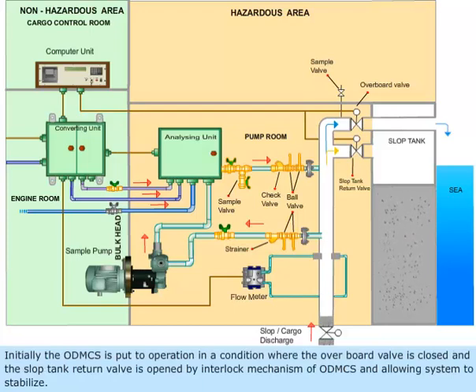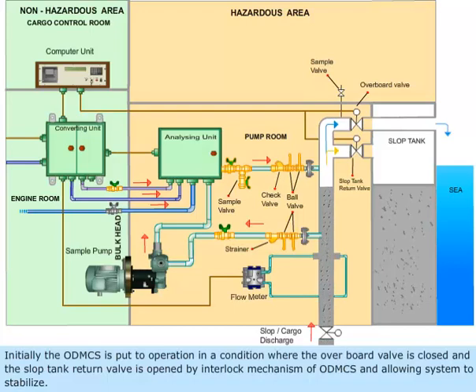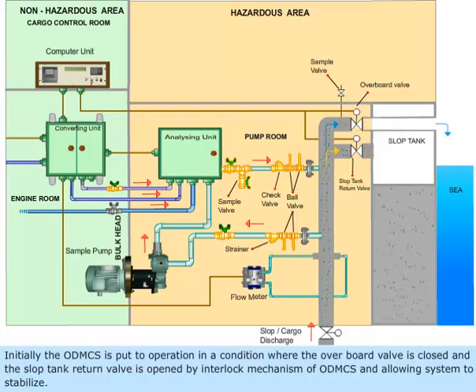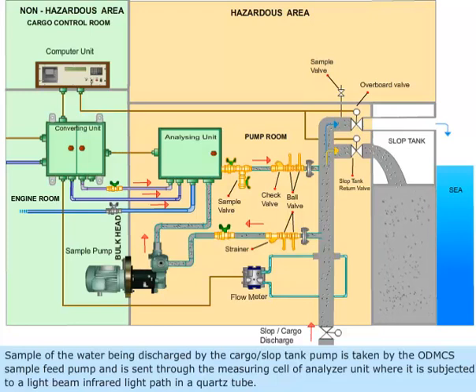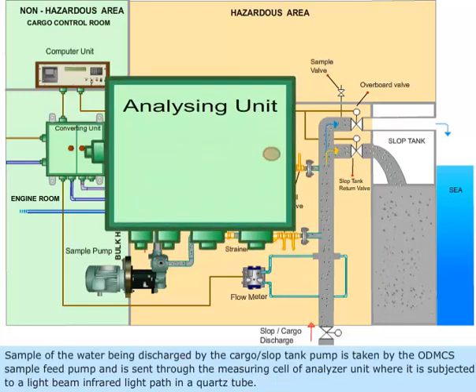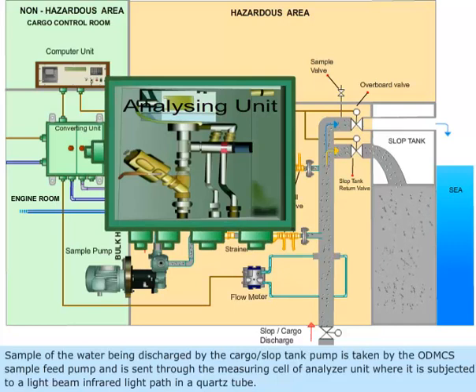Initially, the ODMCS is put to operation in a condition where the overboard valve is closed and the slop tank return valve is opened by interlock mechanism of ODMCS, allowing the system to stabilize. A sample of the water being discharged by the cargo or slop tank pump is taken by the ODMCS sample feed pump and sent through the measuring cell of the analyzer unit, where it is subjected to an infrared light beam in a quartz tube.